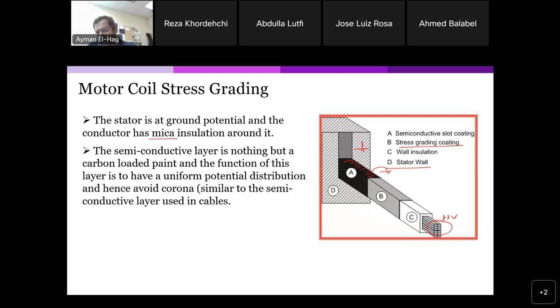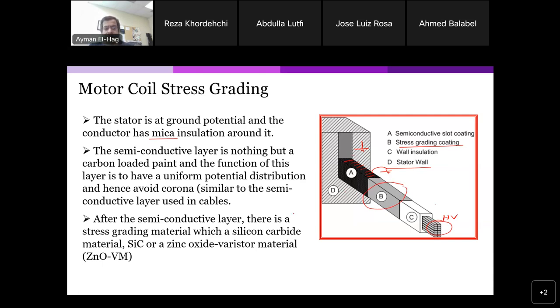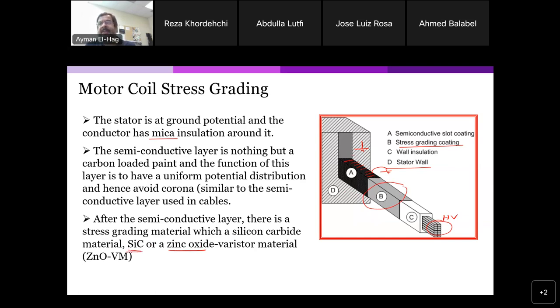Beyond the semiconductive slot coating, a stress grading material is applied. Two types exist: the older silicon carbide (SiC) and the newer zinc oxide (ZnO) — the same material used in surge arrestors. Both are resistive, but ZnO is non-linear, which allows better stress grading performance.